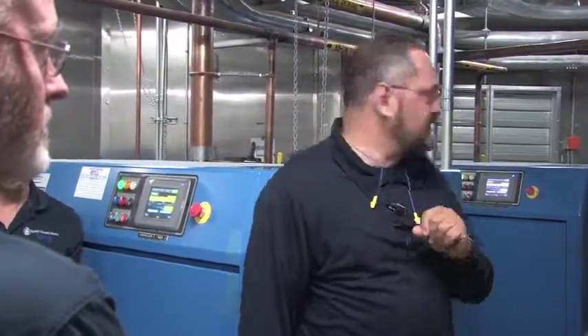And if only one's in standby or only one's running, it'll start another machine figuring, wow, pressure's really going down, can't take a chance, we don't want to ever drop below 80, up we come. Right now it's set so if it drops 10 pounds in that pulse, it'll bring on all three simultaneously. Lag alarm will come on. And if all three of them come on, the lag alarm will trigger.